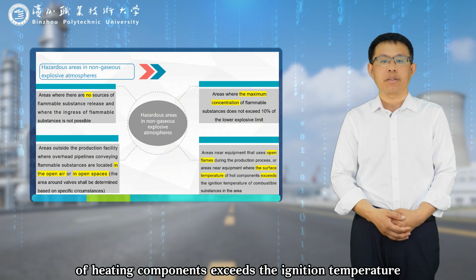Fourth, open air or exposed sections of overhead pipelines transporting combustible substances located outside the production facility area. However, the classification of areas around valves is determined based on specific circumstances. The classification of hazardous areas in explosive dust environments is determined based on the quantity of explosive dust, its explosion limits, and ventilation conditions. Explosive dust environments are classified into zones 20, 21, and 22.